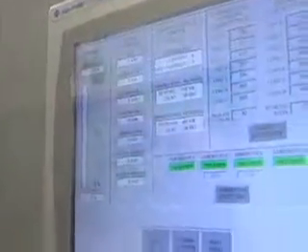On the display you can see our load capabilities for a generator, our power monitoring levels, and which generators are actually online. It can give us all of our demand sequencing — we have eight levels of demand for power in this community between stepping up and stepping down on power. It also tells us if generators are in preferred mode, which basically means that unit is ready and available to run.